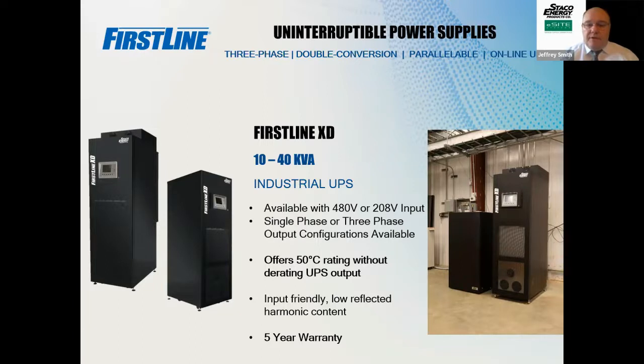The industrial UPS, we're working on even some new systems for more heavy industrial. This is a very light industrial unit. It's for systems that can go into a hotter environment. But one of the things you have to watch for in hotter environments is that the unit can handle it, but it's the batteries that are usually where there's an issue. It is a very good thing that we can actually do a 3-phase in, single phase out. You get a lot of industrial type systems where they have 480 in but they want 120, or they want just 277 out. We're able to do it with this system here. Next slide.